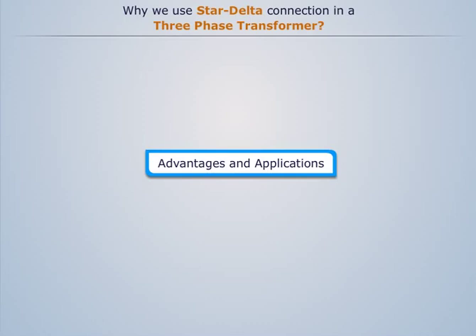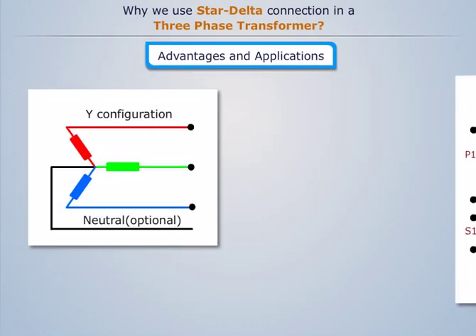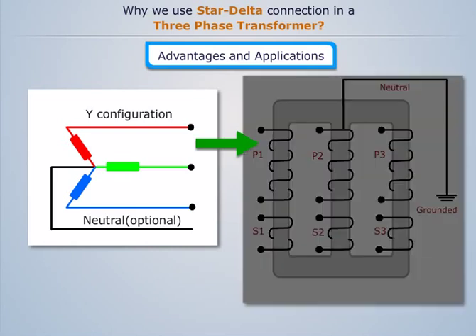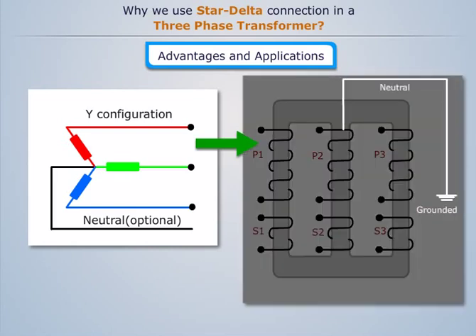The primary side is star connected, hence fewer number of turns are required. This makes the connection economical for large high voltage step-down power transformers. The neutral available on the primary can be earthed to avoid distortion.